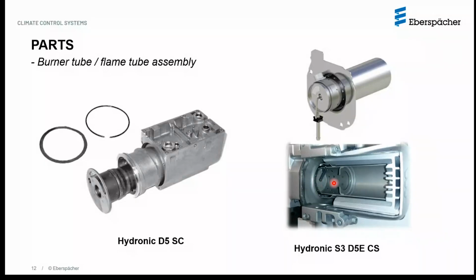So based on this new design of an evaporative mat, you can see there is no need for a glow pin screen, which I described in the previous slide. So that's one less service part that you have to worry about in the newer generation heater. Also, because this is a much larger opening, it's not like a bottleneck as in the previous design. The chances of this heater failing because of a small speck of carbon are highly unlikely. So the reliability factor of this heater goes way up.